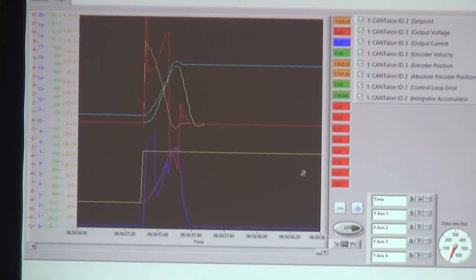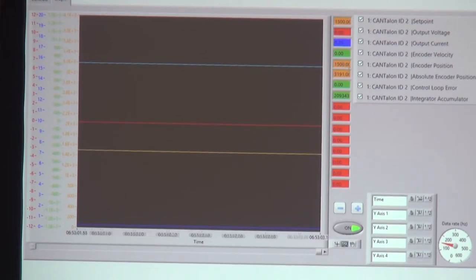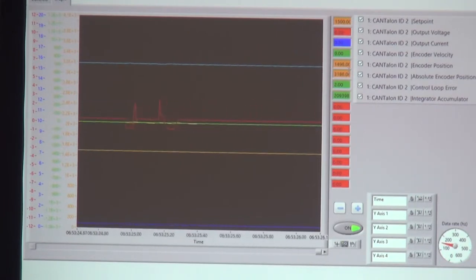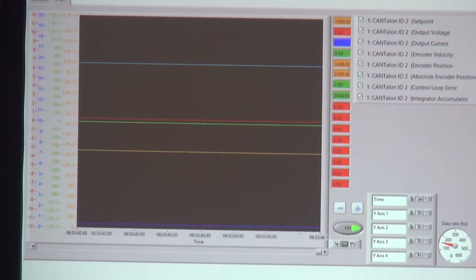One quick request — can you have your graph running while you try to turn the motor by hand? Right here we're sitting at 1500. As I start to back that way, see my voltage coming up? I'm at 1501, then 97 counts — at eight-tenths of a volt, that motor is pushing hard enough on that 100:1 gear train, you're going nowhere. If I put a breaker bar on this, I could maybe move it five counts. Five counts is about three-tenths of a degree. So that azimuth is locked to three-tenths of a degree with or without a breaker bar trying to take it the other direction.